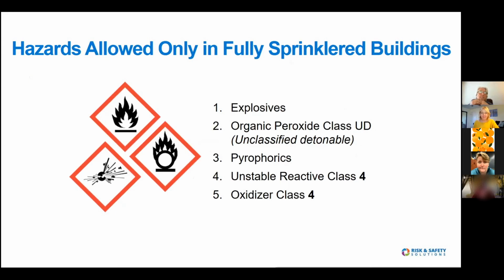So the hazards that are only allowed in a fully sprinklered building in the modern code, so from 2016 to current, are explosives, organic peroxides, unclassified detonatable, pyrophorics, unstable reactives class 4, and oxidizers class 4. Those are only allowed in fully sprinklered buildings.